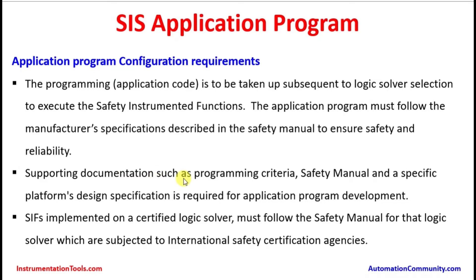Supporting documentation such as programming criteria, safety manual, and a specific platform design specification is required for application program development. Each manufacturer has to prepare a safety manual for diagnosis and troubleshooting on their CPU, processors, input/output modules, and communication modules. They need to provide the different failure rates, as all manufacturers must undergo testing per requirements set by international agencies like IEC, ANSI, and ISA, with results verified and approved by the respective agencies. SIFs implemented on a certified logic solver must follow the safety manual for that logic solver, which is subject to international safety certification agencies.